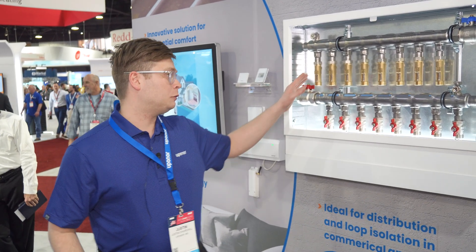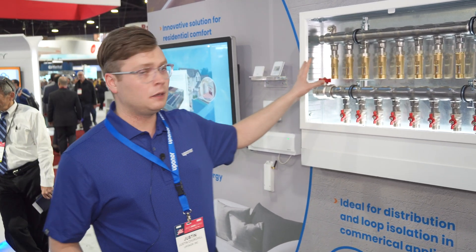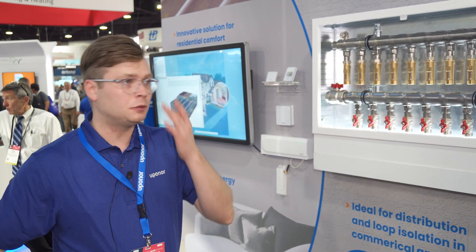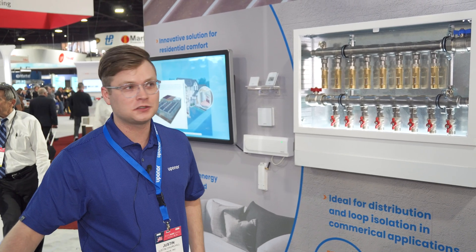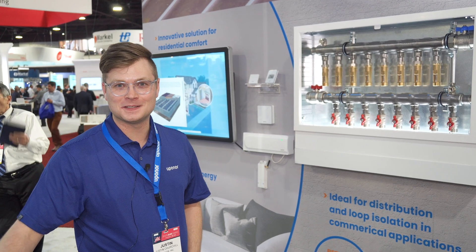This manifold is capable of delivering four GPM per loop, with a total cumulative flow of about 48 GPM for the whole barrel. It's available in up to 12-loop configurations, capable of handling your most aggressive snow melt, ice melt, radiant heating, and turf conditioning needs.